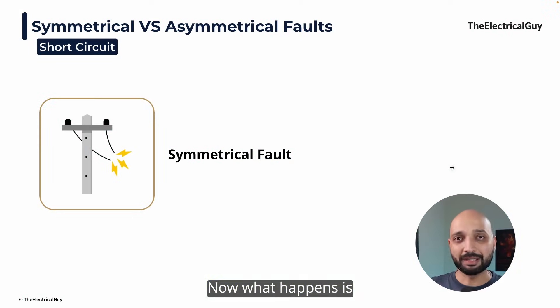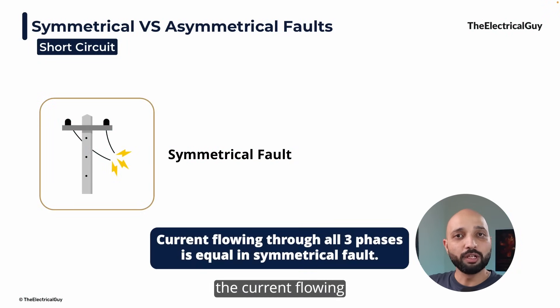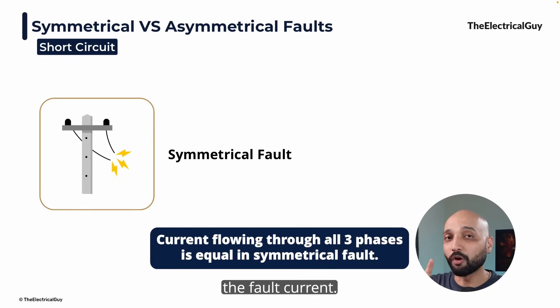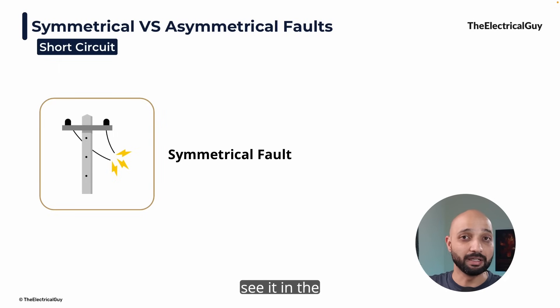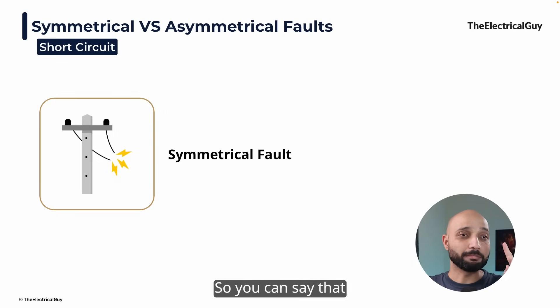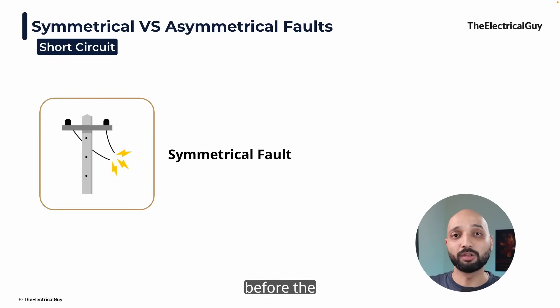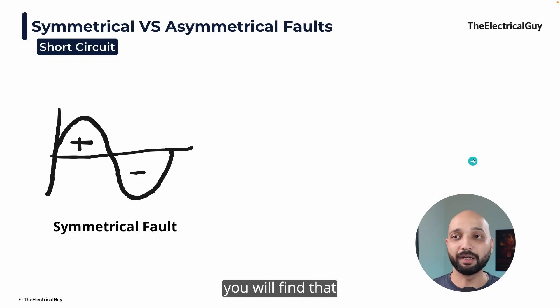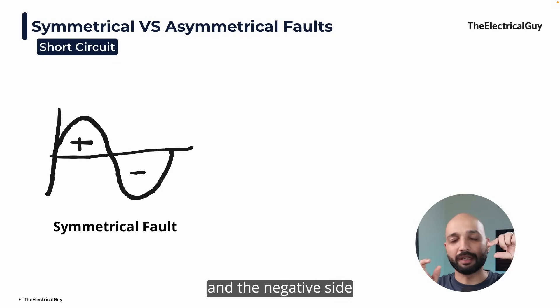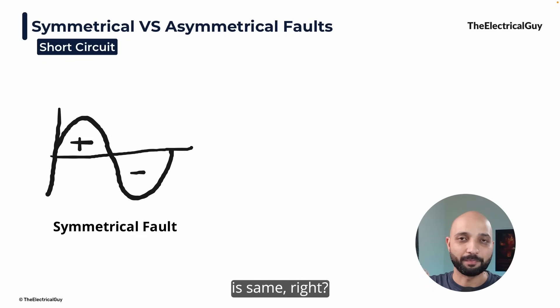Let's start with the symmetrical fault. What happens when this type of fault occurs is that the fault current flowing through all three phases is equal. Whatever fault current is flowing through R phase, Y phase and B phase will be the same — identical. All three currents will still be displaced at a 120-degree angle, as we see in the normal condition. So the system was in the balanced condition before the fault occurred and the system is still in the balanced condition even after the fault. If you look at the waveform of current in any one of the phases, you will find that the positive half cycle and the negative half cycle are the same — there is perfect symmetry. That's why they are referred to as the symmetrical fault.